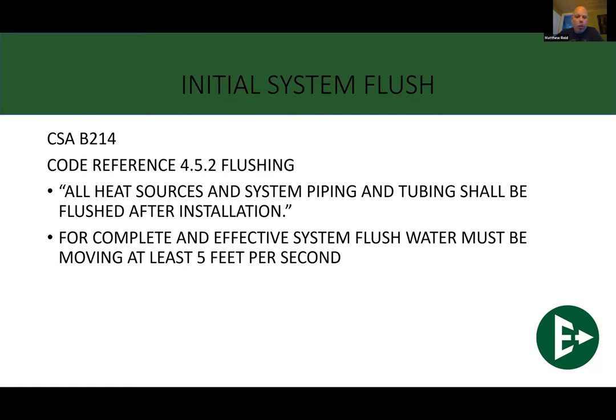Five feet per second is what we're looking for to get crap out of a system. I know the question is, how fast is 5 feet per second? It's fast. You want to move this water through here. Again, you're doing a flush pretty much as fast as you can. I have a lot of friends in the industry who will use recycled hot tub pumps. Those are designed to move a lot of water really fast. You hook that up to a fill and flush cart or a 50-gallon drum with a couple of pipes connected to either side of it and zip that water through it.